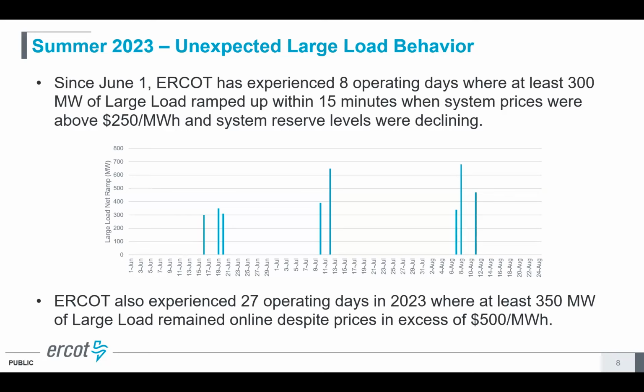Just looking back at the past summer, which was quite hot and had quite a few tight operating days, we identified 8 where at least 300 megawatts of large load came back online late in the afternoon when the system was tight and reserves were declining, and system prices were above at least $250 per megawatt hour. Many of these large loads have slightly different strike prices where their economics shift from being economical to uneconomical to consume. But conservatively, $250 a megawatt hour should be a point where none of these loads want to consume. So that was a disturbing first look, as we're seeing loads ramping 300 to 600 megawatts when the system is tight and we weren't expecting it.